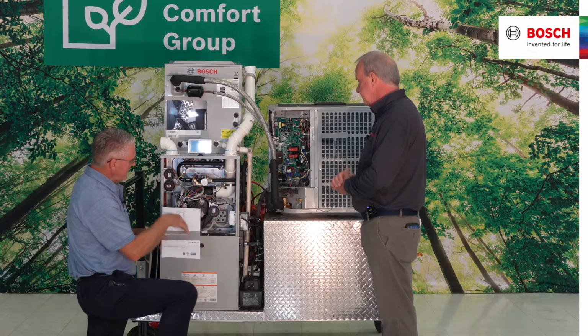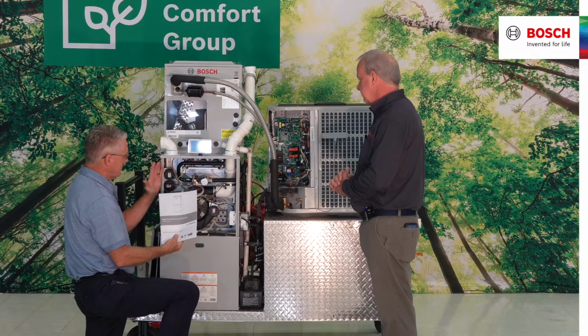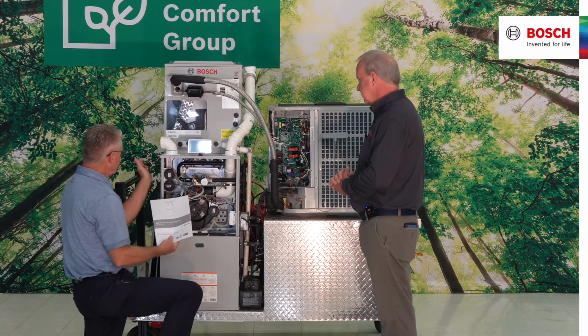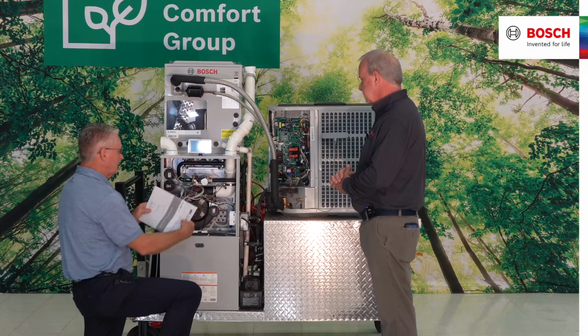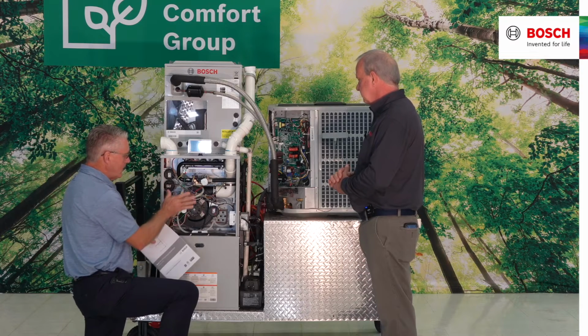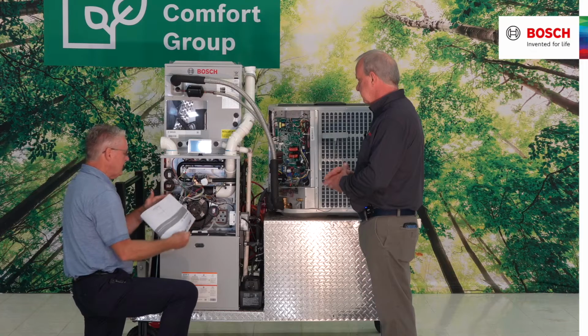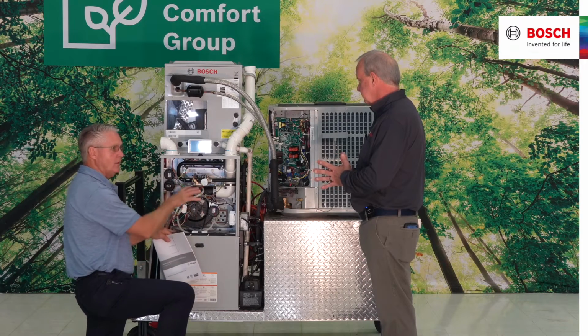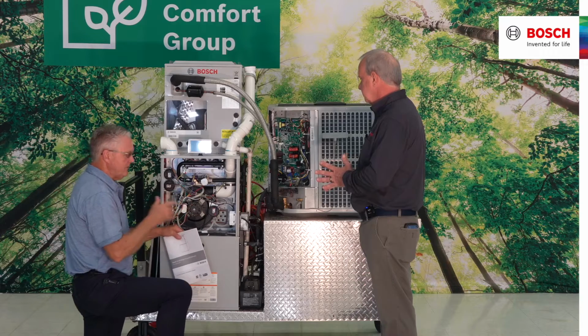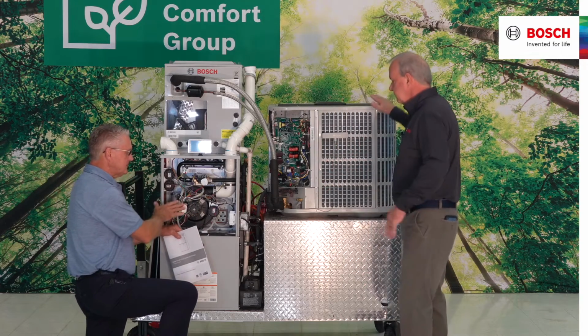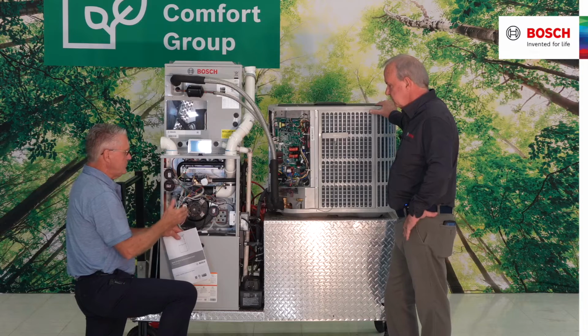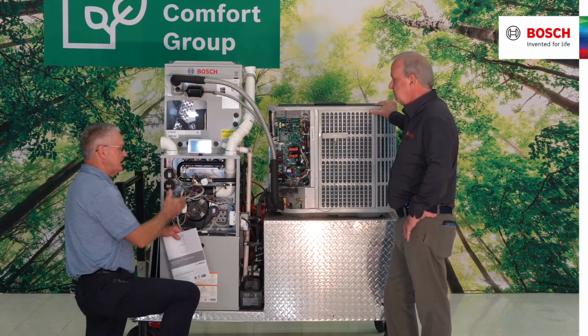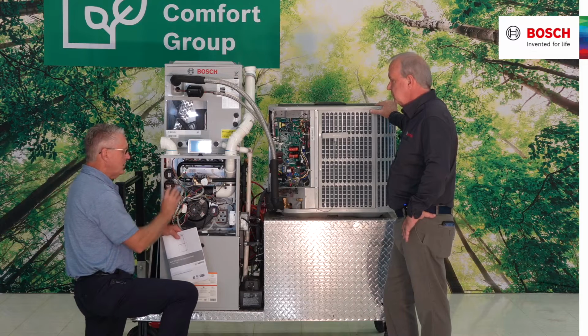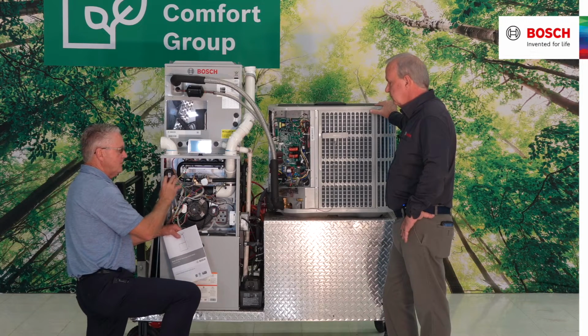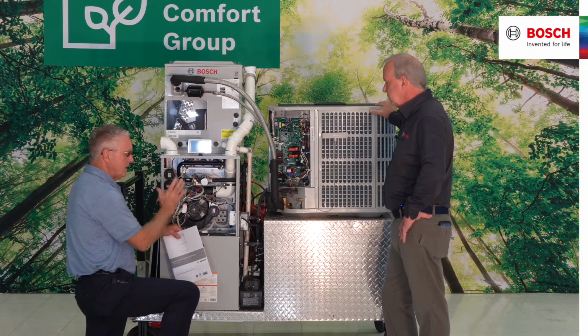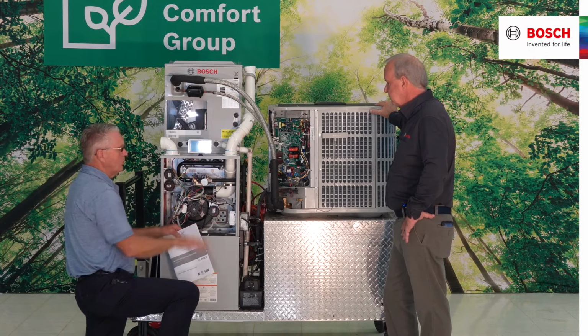Yes, sir. So in the manual, it is going to ask us to tilt this furnace, whether it's in an upflow application from the back toward the front, or in a horizontal situation from the back to the front. Always tilt it 3/4 inch to 1/2 inch of fall, so that I get that water out of that collection plate. One of the things we found out is that if we don't tilt it, we will not get the BTUs that the machine is supposed to give us in a high fire situation, because of the reduction of BTUs that are left inside. We will not get the fire out of it. So we do want to tilt that.